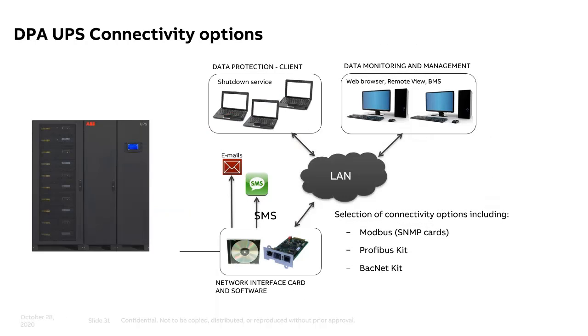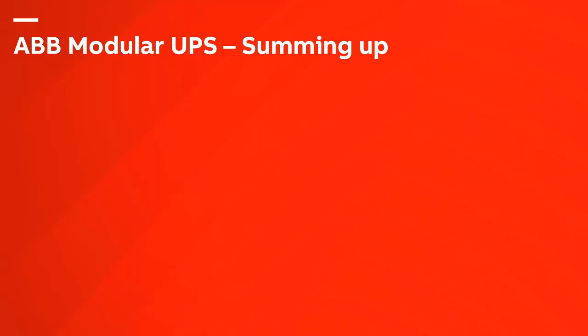And then again, this slide shows the connectivity options for the modular UPS, but this is true across the board. Most data centers use Modbus, smaller ones tend to prefer SNMP. But we support BACnet. Profibus was actually fairly new to me, but is very well known in Europe. So maybe I should have known. It's a protocol primarily used in industrial applications in Europe, but there are customers using it in the US also. So the short comment on that is, do you support that? Yes.